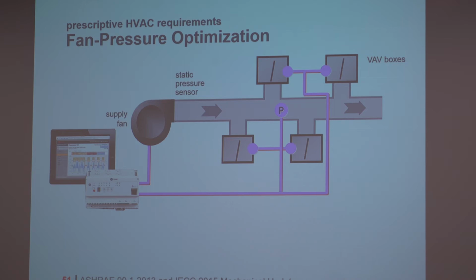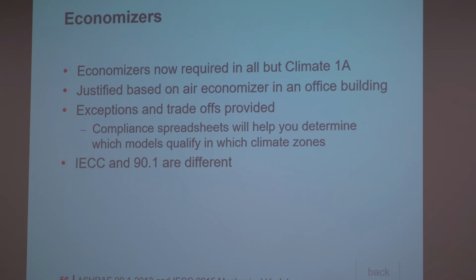So we look at this, and this threshold is coming down. It used to be larger systems. It's coming down to smaller and smaller systems. And generally people accomplish this with a VFD on the pump. If you want to do it with pump pressure reset based on critical valve, you have to have data about the valve position, so it requires some DDC controls in your space. We'll talk about that a little bit more in a bit.